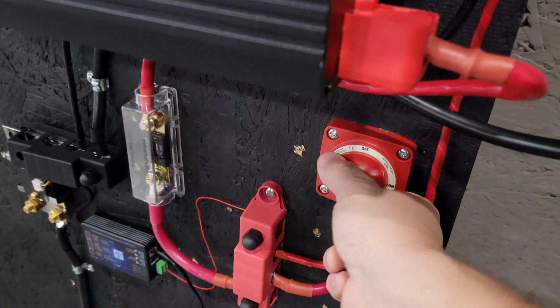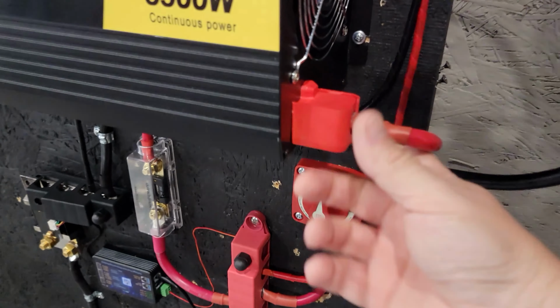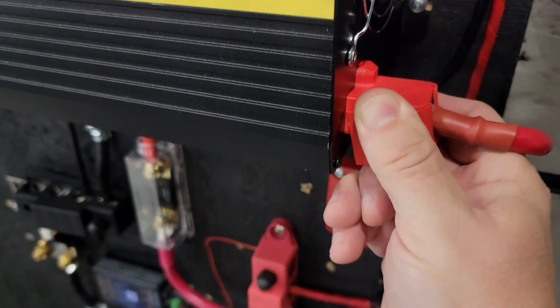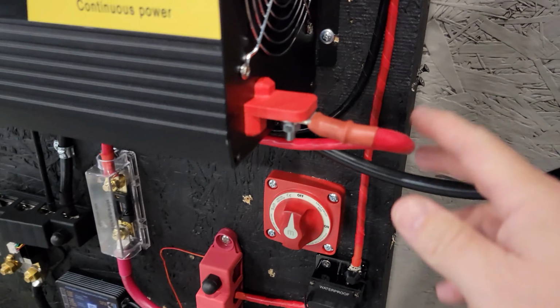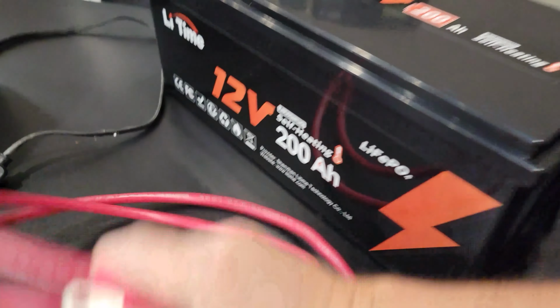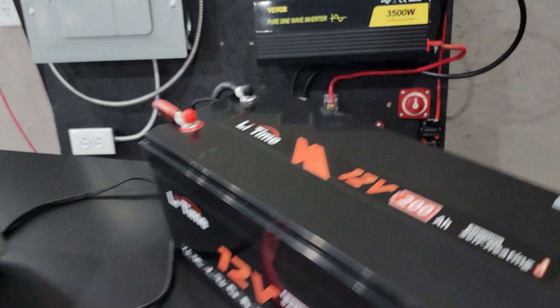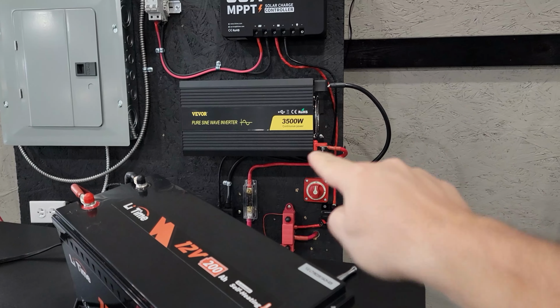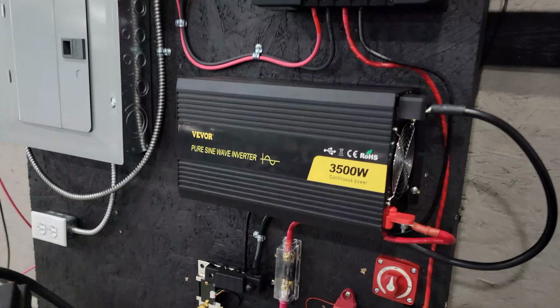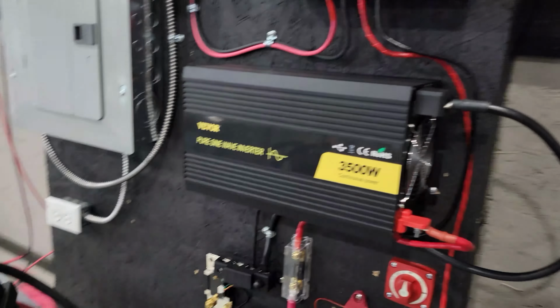You want to see real life testing, and I want to make sure the BMS in this battery does what it says it's supposed to do. First, let's turn the system back off, take this cap off. We're going to remove this and this, and add this cable directly to the inverter, bypassing everything we have going on here. And we'll find out if that BMS will protect the battery.